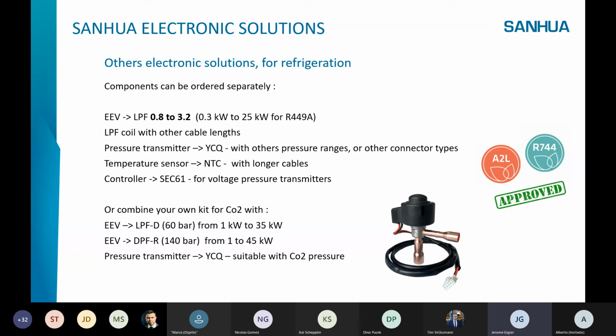And if you have a CO2 application, we have 2 models. The LPF-D has a maximum pressure of 60 bar, for capacity from 1 kilowatt to 35 kilowatts. And if 60 bar is not enough for your application, you can use the DPFR, which we also have in the catalog. DPFR is an expansion valve suitable for 140 bar. We have 3 models, from 1 to 45 kilowatts. And we also have pressure transmitters specific to CO2 applications.